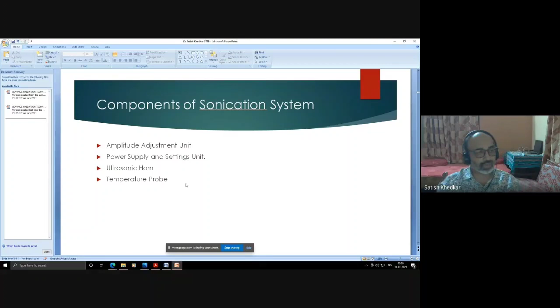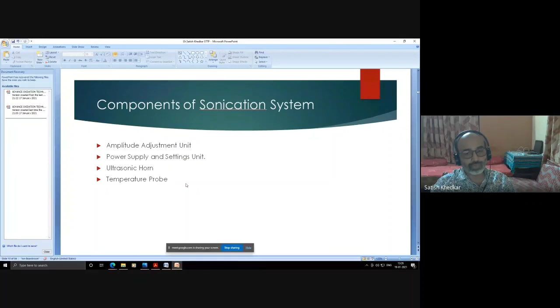Then a separate temperature probe is there so that you can check the temperature of the sample which is being sonicated. In case the process is temperature sensitive, then you can control the temperature by means of external cooling. You may provide cooling jets around the sample which is being sonicated, and you may circulate cooling fluid through the reaction vessel where the reaction is taking place, and you can remove the heat from the reaction zone by using some kind of fluid which is good in heat transfer. So that fluid may be used. Often water is used for removal of heat, but depending on the sensitivity to heat, you may use different liquids or different fluids also.